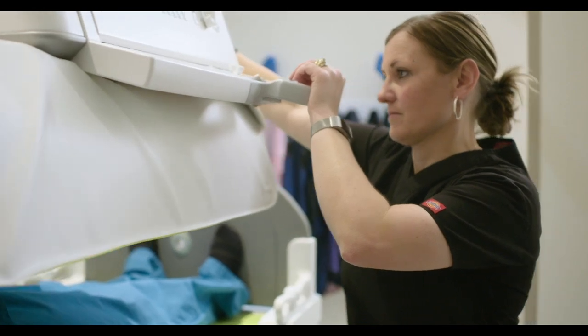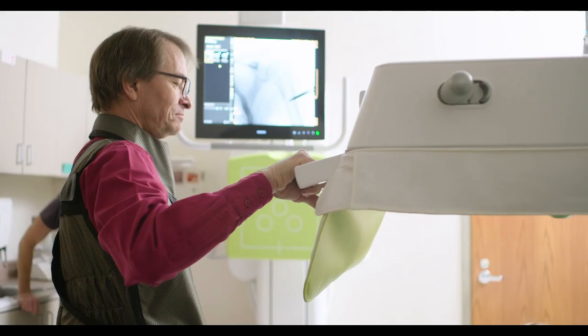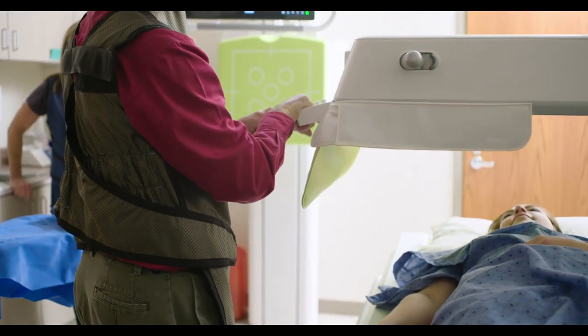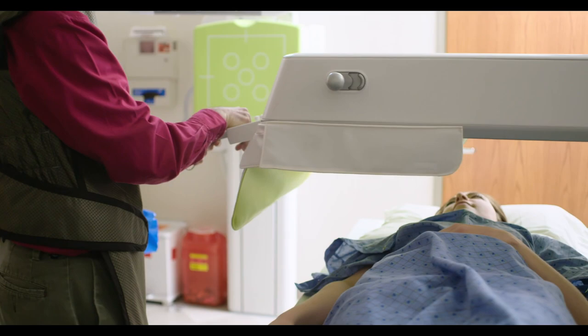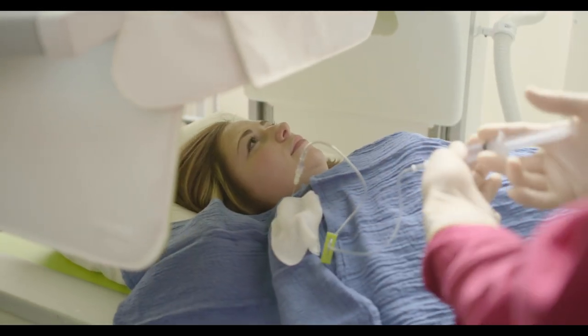The way the equipment runs is basically unchanged, but there's more space. If you have a patient that's claustrophobic and can't take that tower being so close, you can back it off a little bit. When you start to back it off on the prior machines, you notice it instantly on your image resolution. With the ProxiDiagnost, your image resolution is much better at a longer distance.